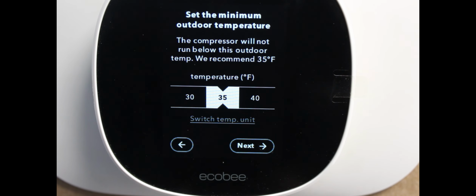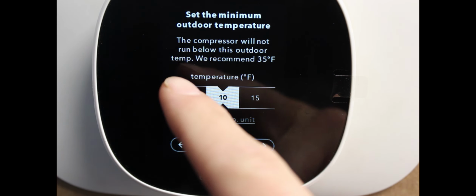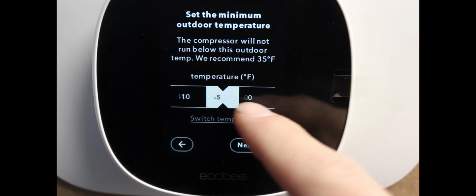Minimum outdoor temperature. So this means the thermostat will not use the heat pump or the outdoor unit below this temperature. It's defaulted to 35 degrees, which is kind of the standard that's been used in the industry for heat pumps. They just tend to lose effectiveness as it gets colder. But with all the new efficiency requirements and the different staging and modulation of equipment, they are much more effective down to low temperatures. On most equipment, you can set that anywhere from 10 degrees to -10.